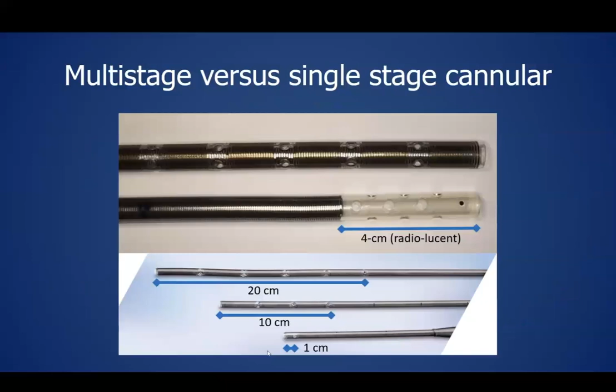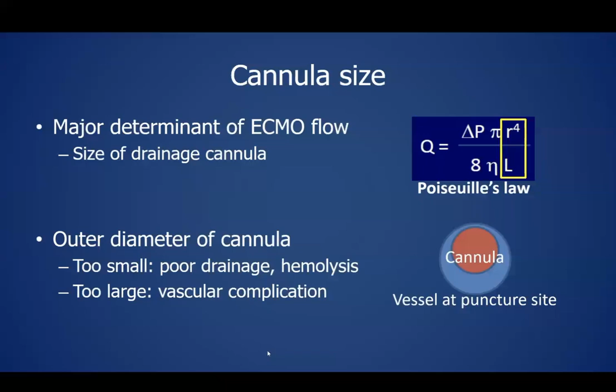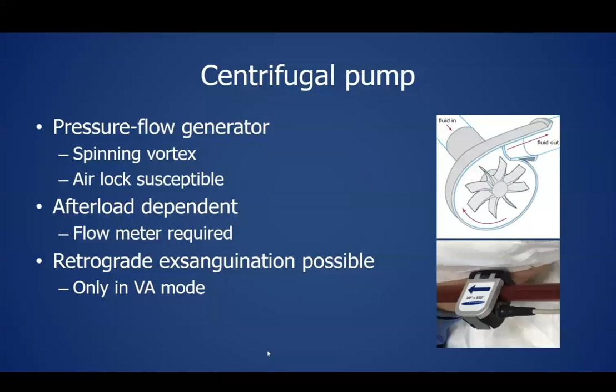The size of the drainage cannula is the flow-limiting factor of the circuit according to physics. A too-small cannula will provide less flow and is at risk for hemolysis if you drive high flow with high RPM. But a bigger cannula is associated with more vascular complications and distal ischemia. The recommended size will be based on the patient size. The size can also be selected based on the blood flow needed. The centrifugal pump is afterload dependent and also susceptible to airlock. A flow meter is always required.